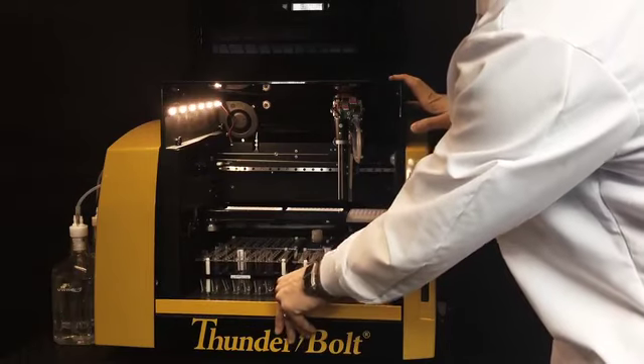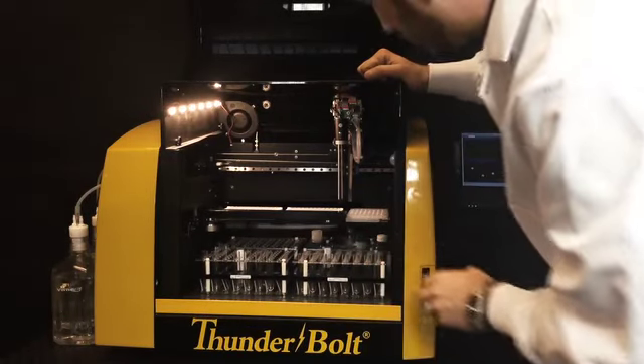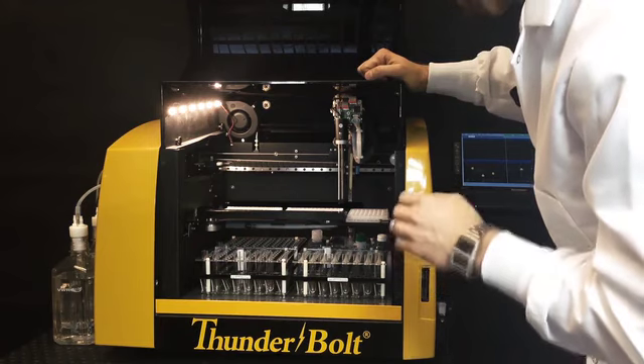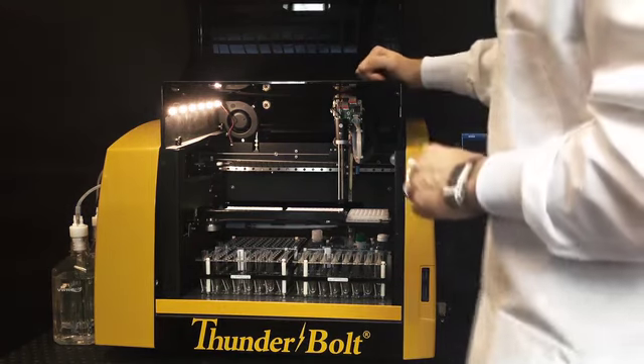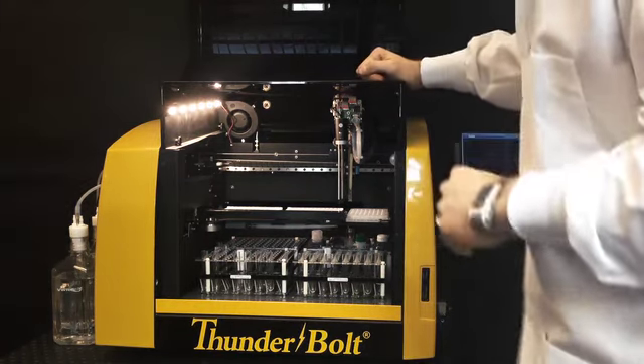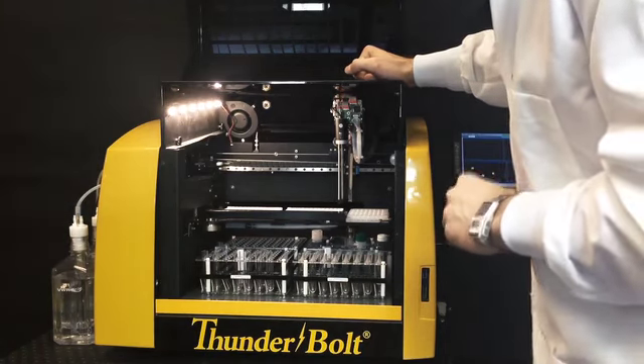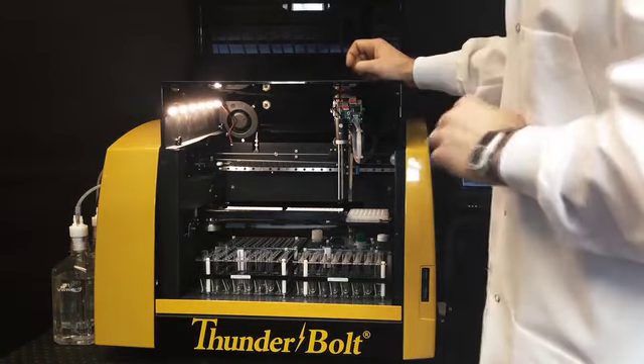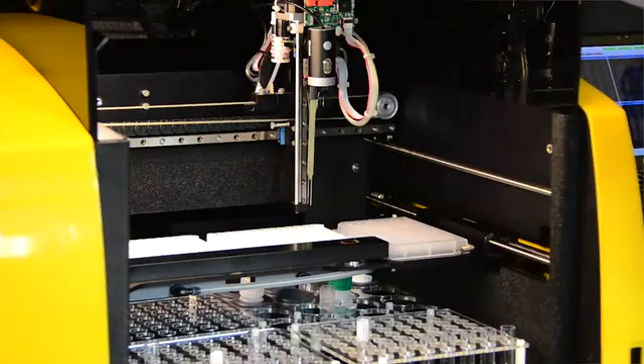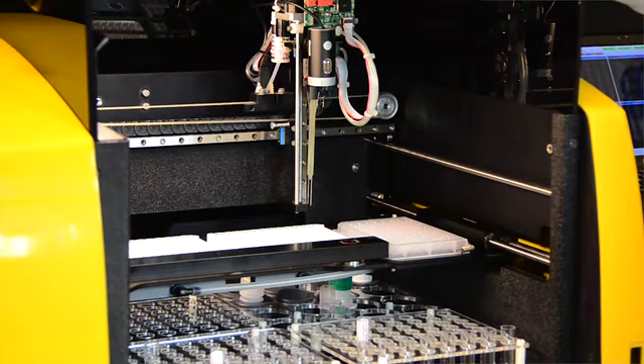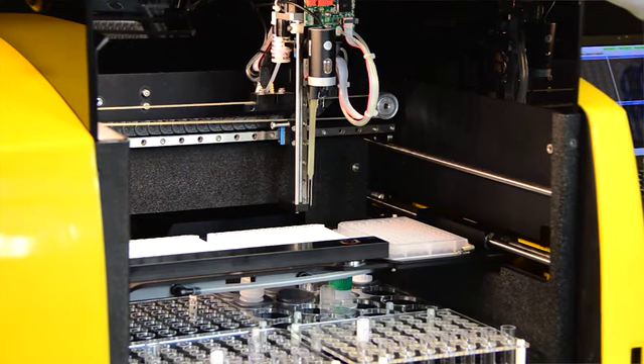Our probe is a single probe dual needle system that accurately can pick up all the way down to 1 microliter with a 3% CV across a full plate. The reason it's able to do that is that we have a micro syringe, which is located directly above the probe. That micro syringe is responsible for picking up all the small volumes, so from 1 to 40 microliters. We have a macro syringe that picks up everything above 40 microliters. Like I said, all critical volumes are picked up with a syringe.